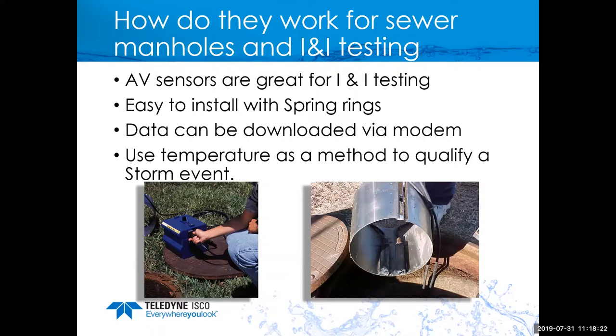So how do they work for sewer manholes and I&I testing? You can use the area velocity sensor. We've been using them for the last 20 years or more for I&I testing. As shown here with the area velocity sensor, it's a great option for I&I testing because it's easily installed. We have a spring ring that you mount the sensor to. You just squeeze it together, slide it in the pipe, let it go, it holds it in place. So you can use that with pipes that are 15 inches and smaller.